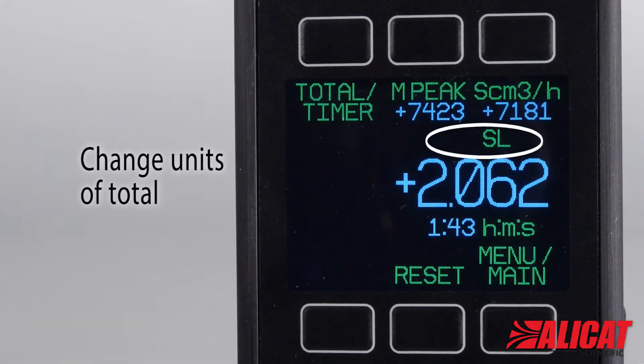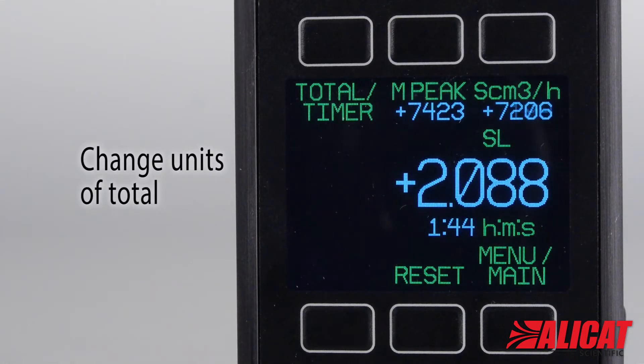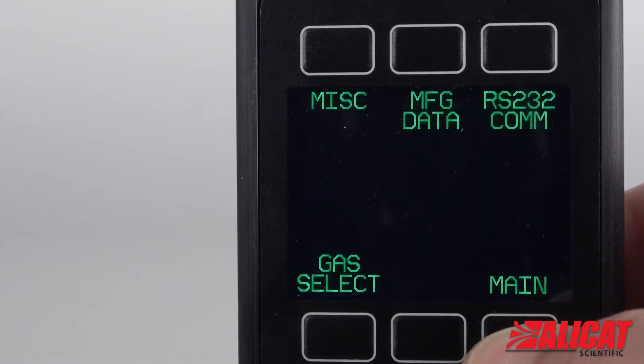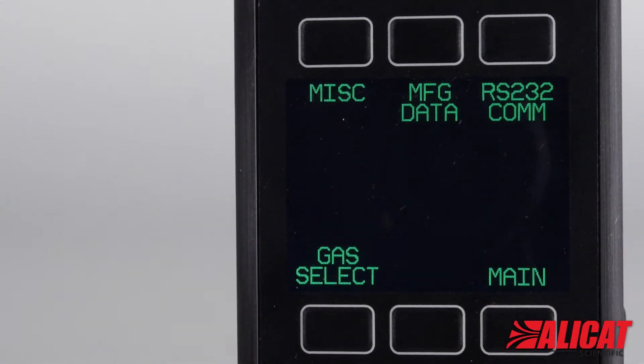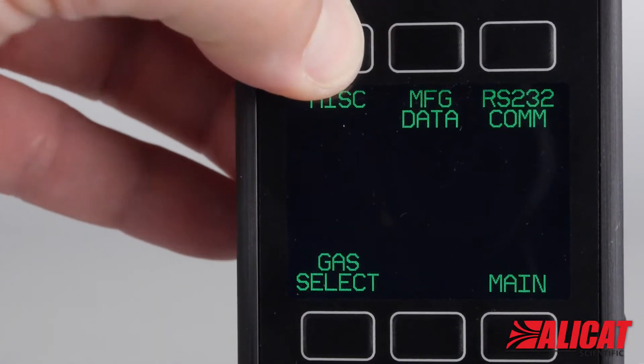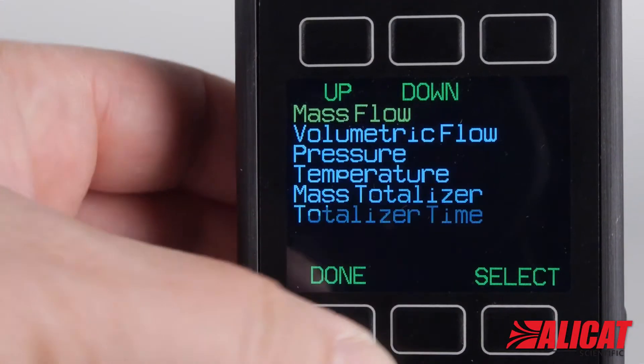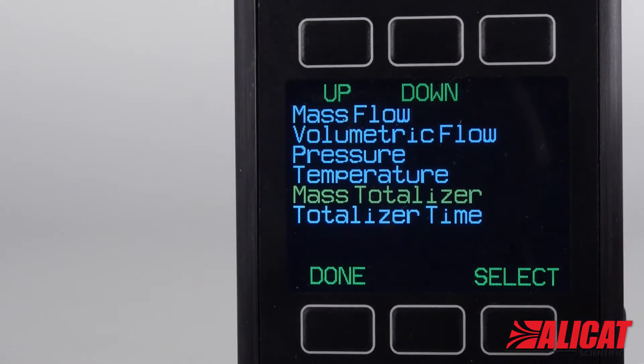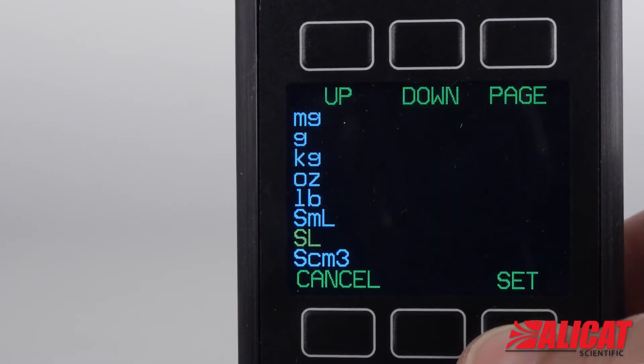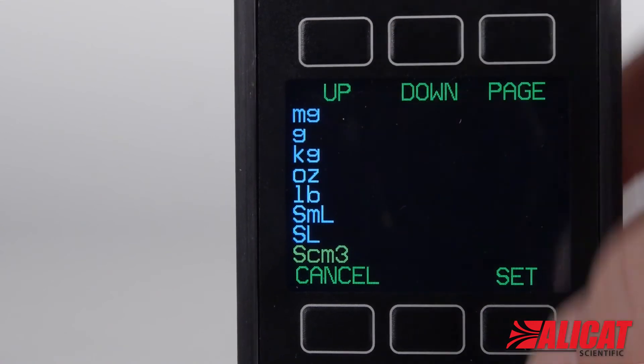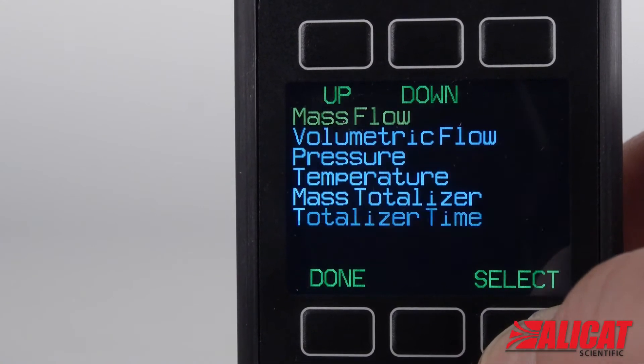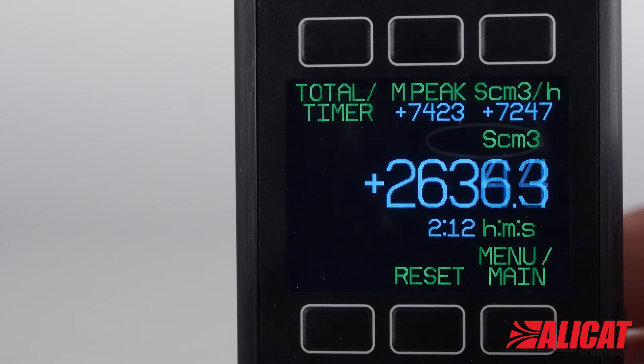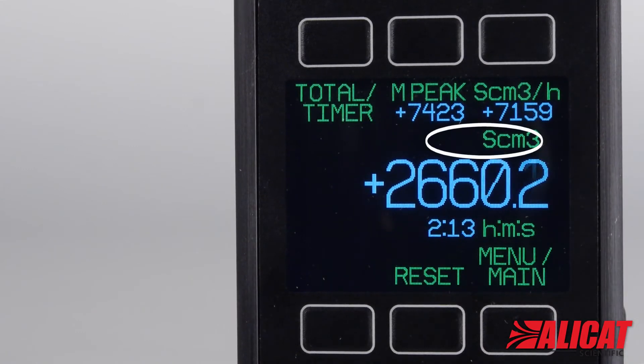To change the units in the total reading, you need to go to the device units menu. Pressing main menu takes you to the menu screen — press miscellaneous and device units. Highlight mass totalizer and press select. Scroll to your preferred unit and press set, then set again to verify. Press done, then backtrack to the main screen and select total menu again to see the change.